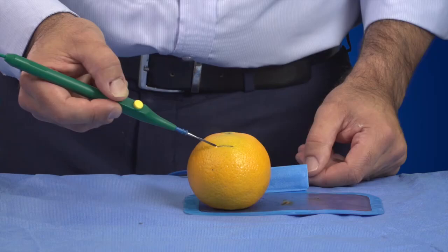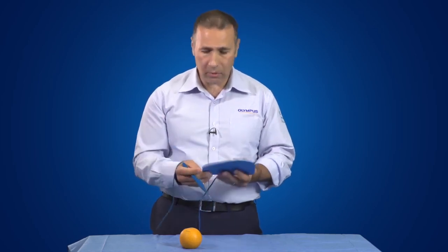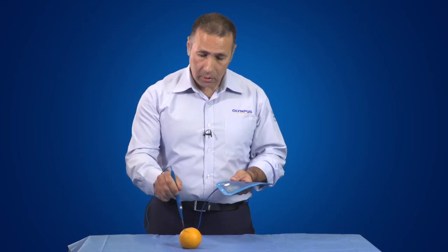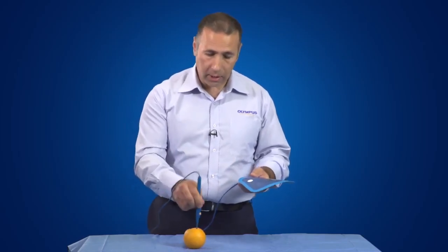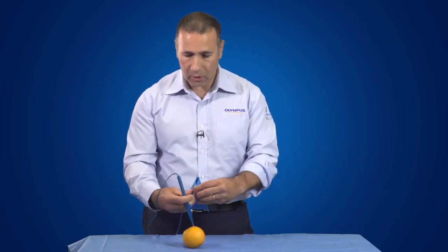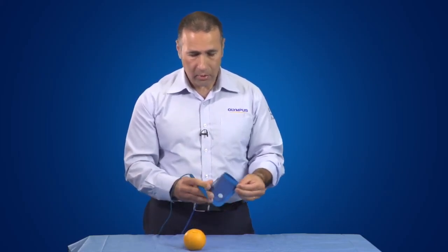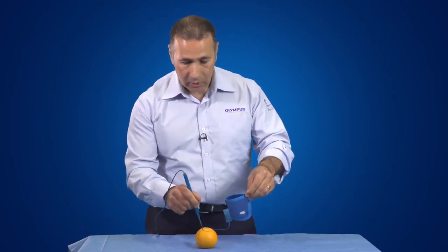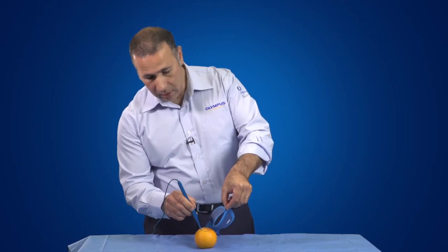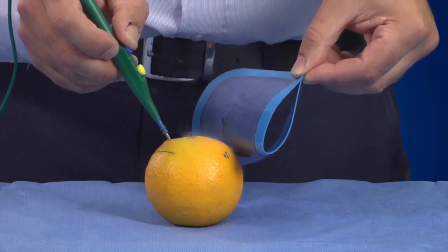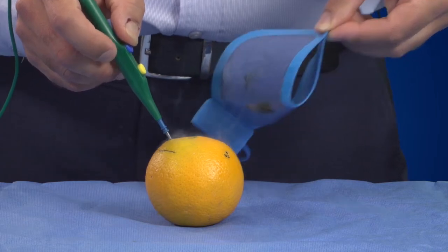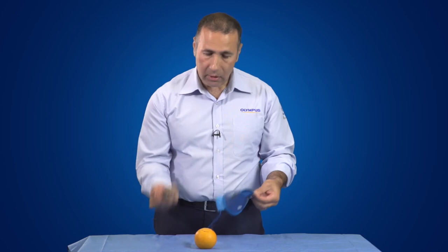I'm going to activate. So there you see I get an effect here, but if I take that off, there's no heat generated there, no untoward side effects. Now, if I change the contact area or the current density associated with these two, so I'm now going to insert the active electrode, or which was the active electrode, into the orange, but now I'm going to change the current density of my return, or what was my return electrode. Now all of a sudden you will see that I elicit an effect through what was the return electrode.